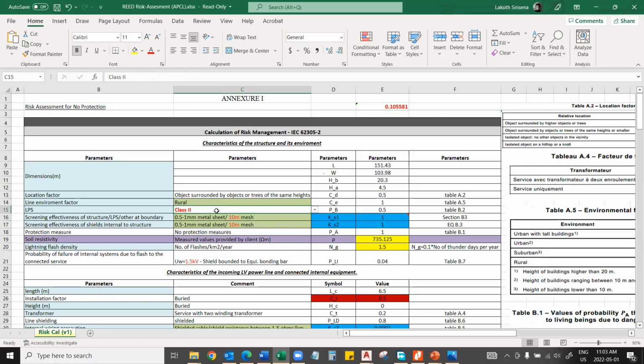And if you already have a fire protection system installed, you cannot, unless it's unavoidable. Now, as the lightning protection system designer, you have to consider the lightning protection class. So depending on the class, it will play a role as we discussed, right? You can see how it changes. So based on that, you have to select which protection class will satisfy our requirements, or what sort of class will be required to address the available risk at the premise. Okay, so if you have a high risk, that should be covered with the class 1. If you have a low risk, then it can be covered with simply a class 4 system.